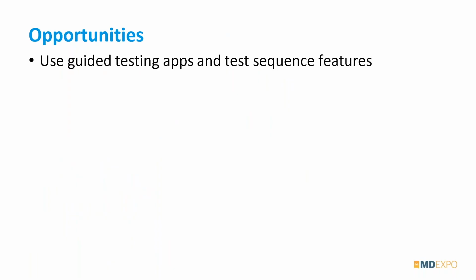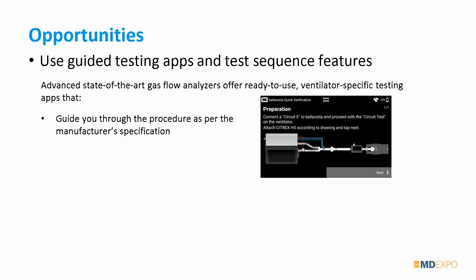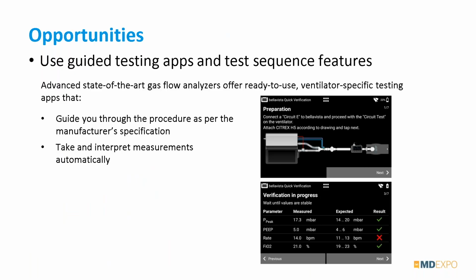So the last opportunity linked to that is, on some gas flow analyzers out there in the market, you have guided applications or test sequences that they offer. Sometimes these applications are on computer software, sometimes they actually run on the device. And what they do is they guide you through the whole procedure, and they can also take the measurements automatically and interpret these measurements. So they can do the calculations for you automatically and then judge whether the result is in the range or not. And then they can give you pass-fail results right on the screen. And also they can save all these measurements and at the end create a PDF report that you can then print and attach to your work order.